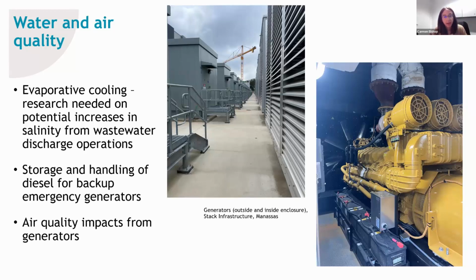Now, with regard to air quality, it is also related to the emergency backup generators, and for that purpose they need an air permit from the Virginia Department of Environmental Quality as well. Those air permits do limit the pollutants; in this case the primary one of concern is nitrogen oxides. They also regulate the time of day during ozone season when they can be tested. These generators are only intended for emergency use and only allowed to be used for emergency purposes, but they do need to be tested and maintained, and typically they are run somewhere between 5 and 15 minutes a month, each one.